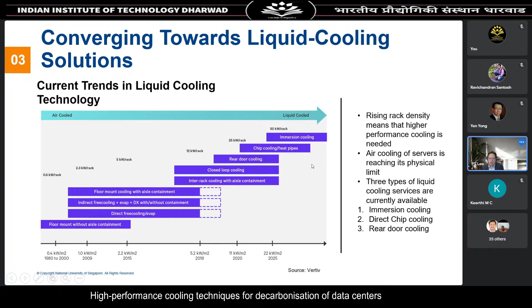The second is direct chip liquid cooling, which my research group and CoolestDC are actively working on. This can easily handle rack density in excess of 25 kilowatts. And going even a step higher, there's a lot of interest in immersion cooling. Again, due to rising rack densities, higher performance cooling is necessary.